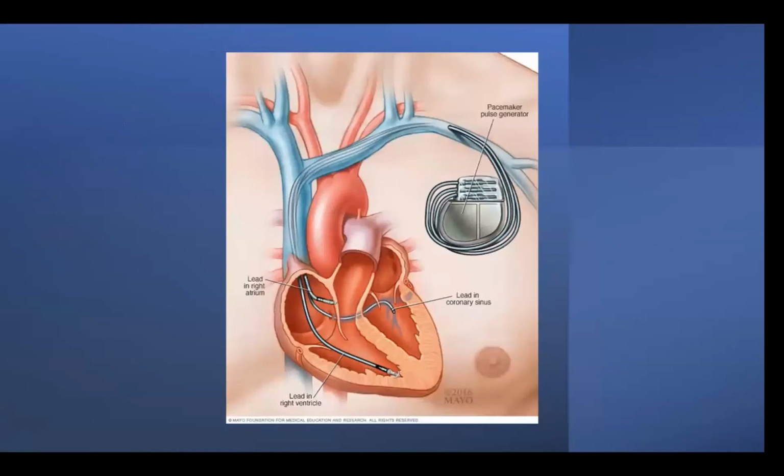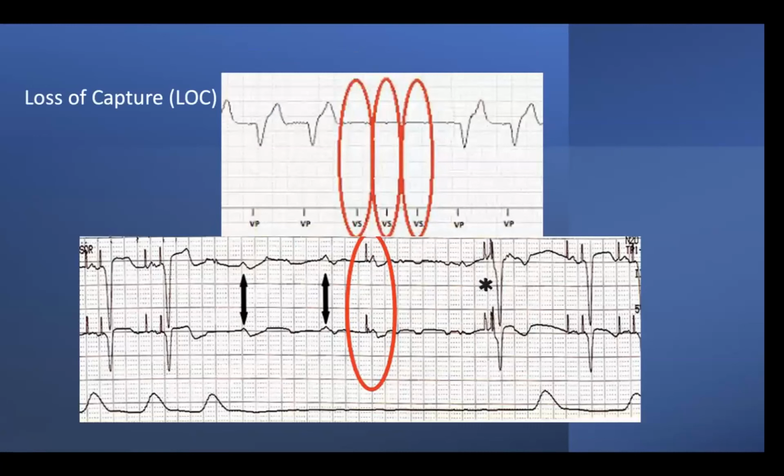So you mentioned, for complete heart block patients, one thing you can always keep in mind too, if you're doing a CRT gen change, if a patient has an LV lead, you can always pace from the LV lead as long as it has a bipolar vector set and it's not set to go to the RV lead. So that's always a consideration if you have a dependent patient: leave it on high output, set the device asynchronous, and then just switch over. You'll have some competitive pacing between the new device and the old device, but you'll never lose a beat essentially. So just things to keep in mind there.